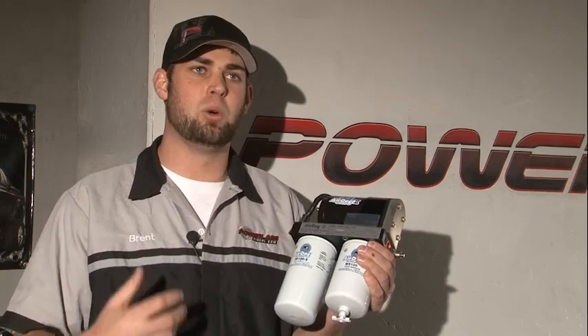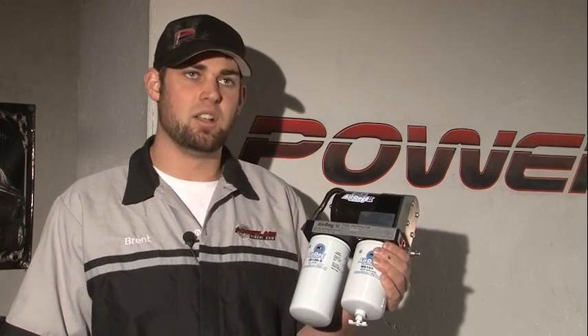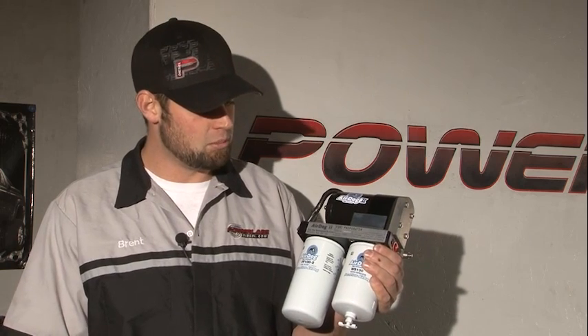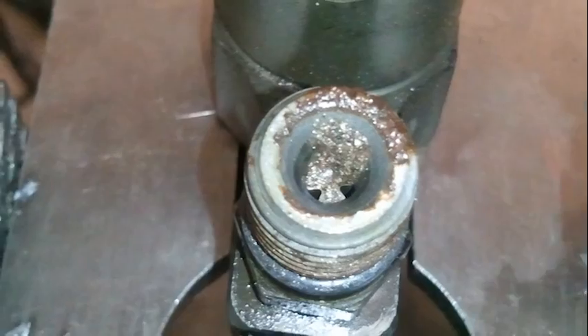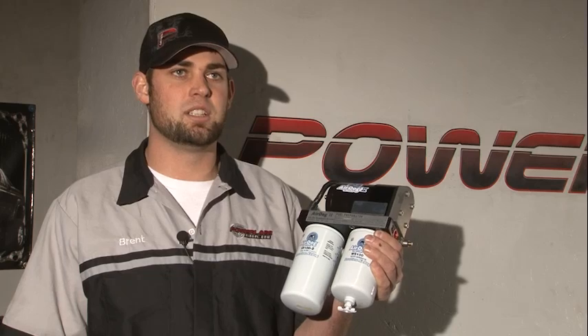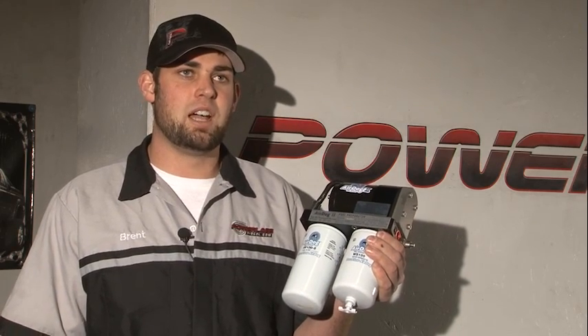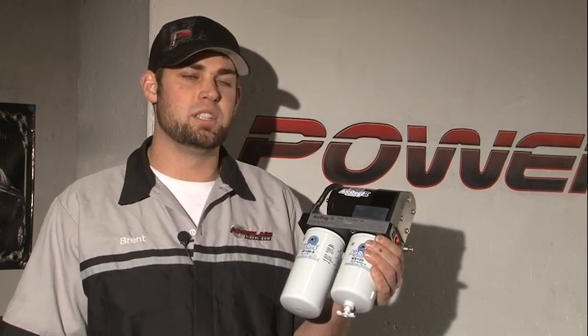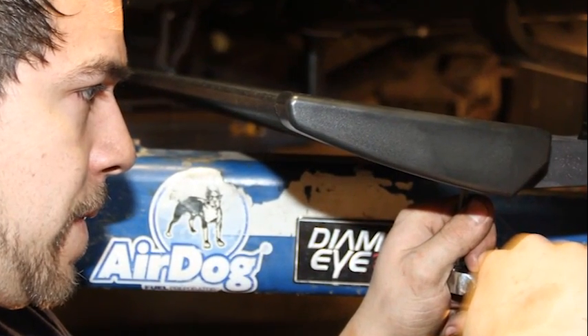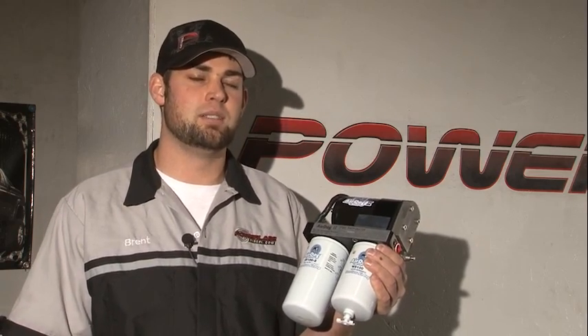The injection pump is pulling from the tank and you get a lot of air. Those microscopic air bubbles cause metal-on-metal contact inside the injector. The diesel fuel lubricates the injector, and if we've got air, we've got cavitation, and we get some wear in the injector. These pumps remove the air and feed a nice, solid, steady stream of diesel, so you don't have to worry about that.